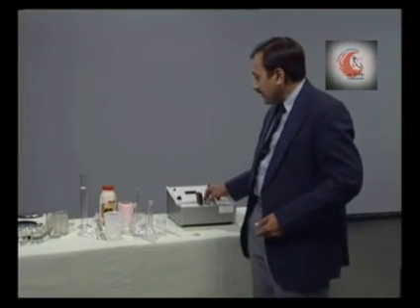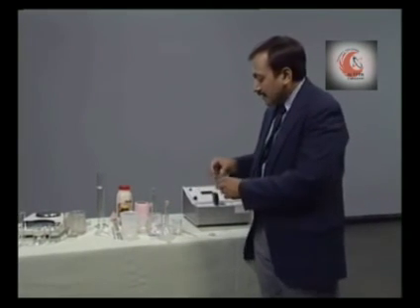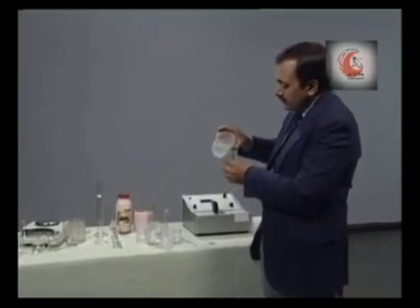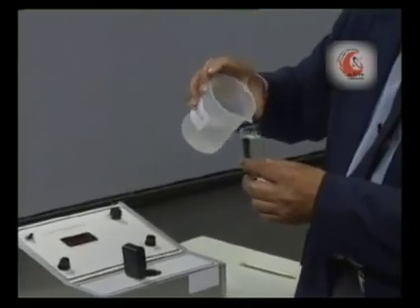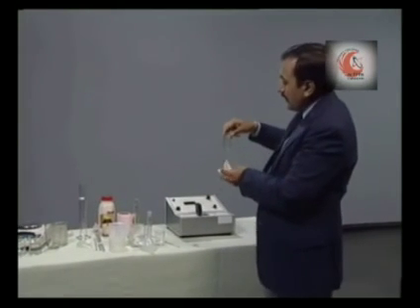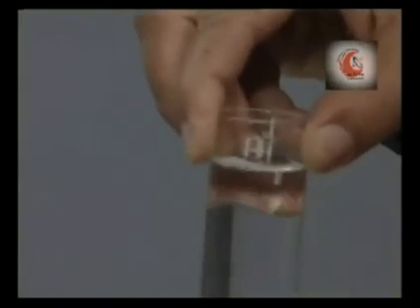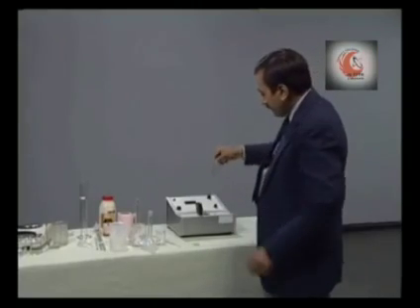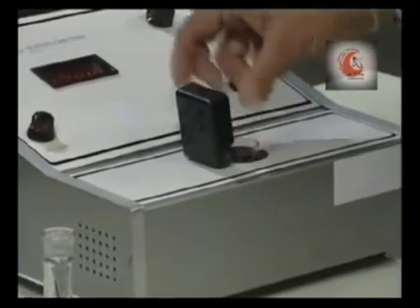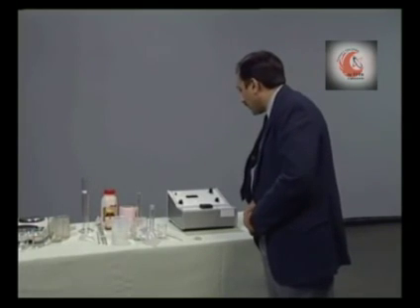Now simply take the sample, remembering that the tube should be wiped of any watermarks, and measure the turbidity value.